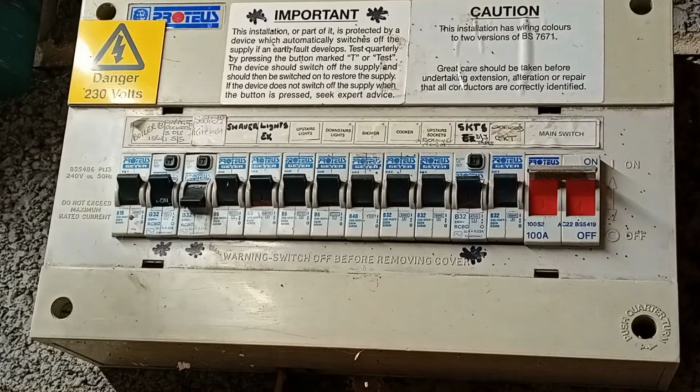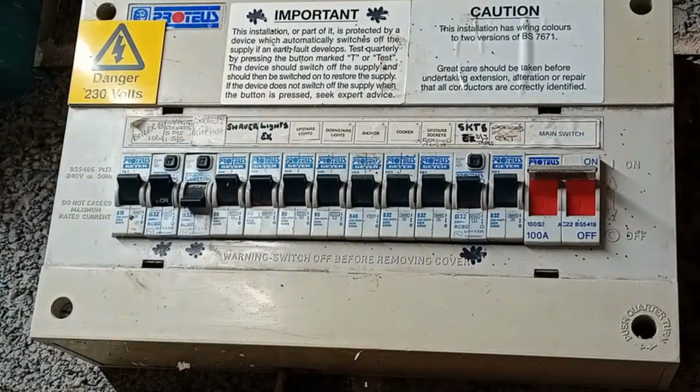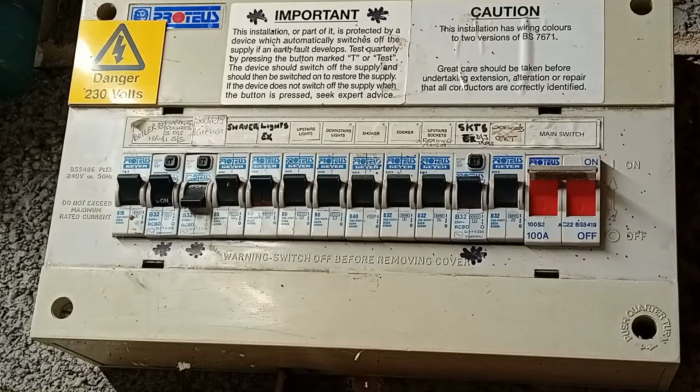So we'll see if it stays in now, which it doesn't. So that's proven step one. It's definitely not an appliance causing the fault on this circuit. So we need to move to step two now. It's either a wiring fault on the circuit, or it could possibly be a faulty breaker, which I've seen before. So the easiest one to check is the circuit breaker. So that's the next thing we're going to check. It's actually an RCBO, is this? So now I'm going to show you how to check if that's at fault.